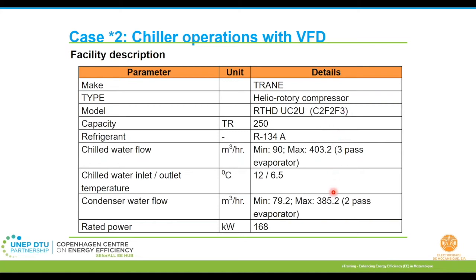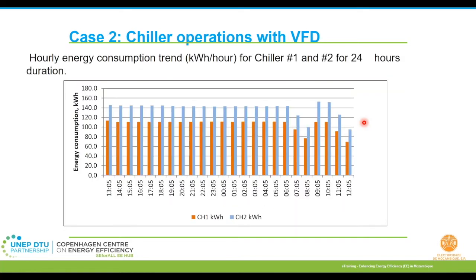The design details of the chiller that was present: 250 TR chillers, two of them. Chiller one was with VFD and chiller two was without VFD. Both were operating under the same conditions. If you look here, the chiller with VFD, the orange one, this is for 24-hour captured data. The hourly energy consumption for chiller one with VFD is low compared to chiller two, though both are subjected to the same cooling loads and operational conditions. Why? Because the chiller with VFD has the flexibility to modulate its power consumption as per the cooling load demand, and hence during low cooling loads it consumes less power than the chiller without VFD.